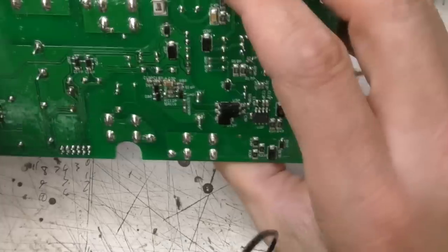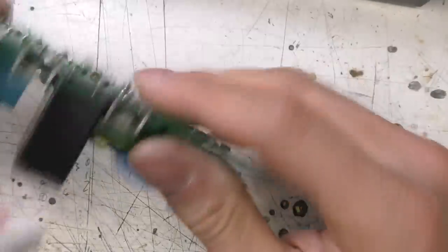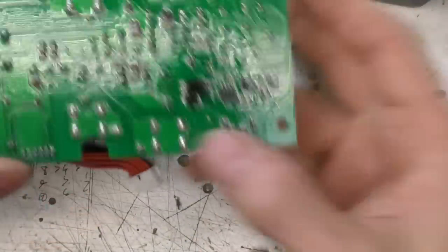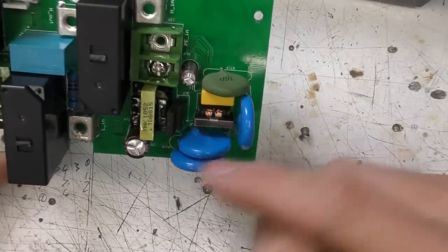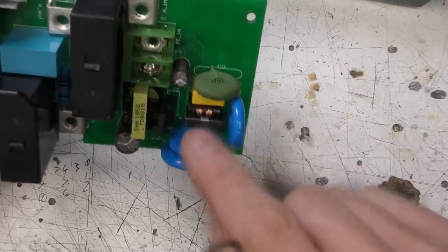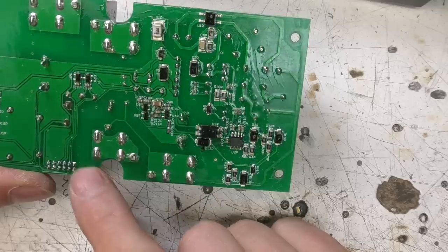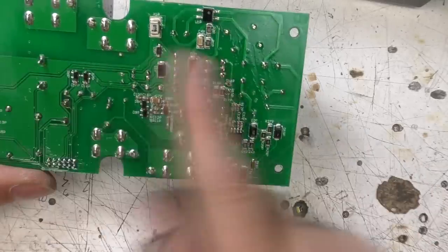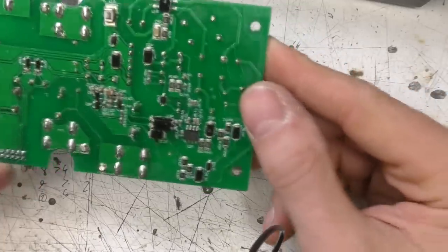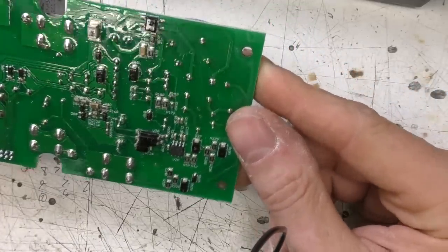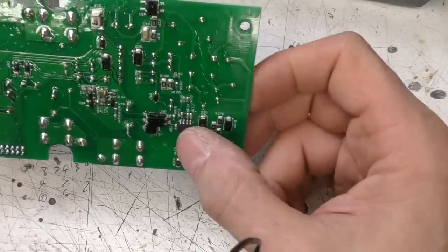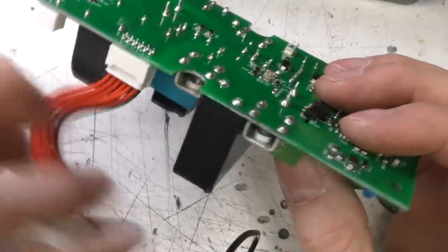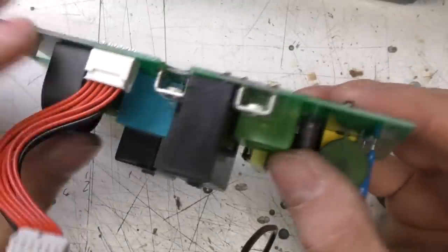Again, I don't think this is a 2-ounce copper PCB, I think this is fairly standard, but again we've got the tracks on both sides of the PCB. Unlike the other one that had a power supply module, this has got a discrete switch mode power supply for its low voltage, but we've got a decent amount of proper filtering and creepage distances on here. Again, both boards have got conformal coating on, so that gives a bit of moisture resistance. This is the power supply control circuitry here. It's got a nice cable connector rather than the FFC cable, and the other one was a little bit fiddly to get on and off. This one's a bit nicer.